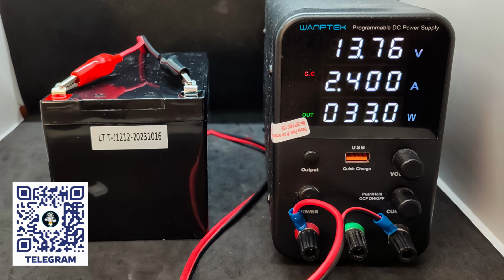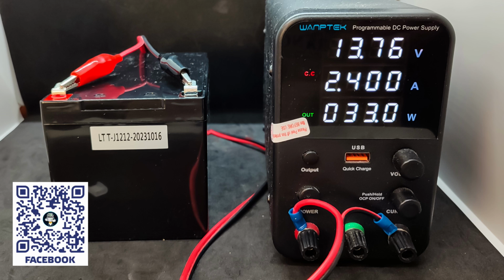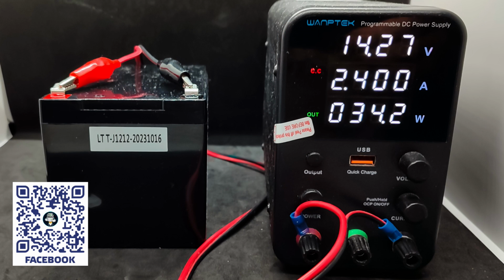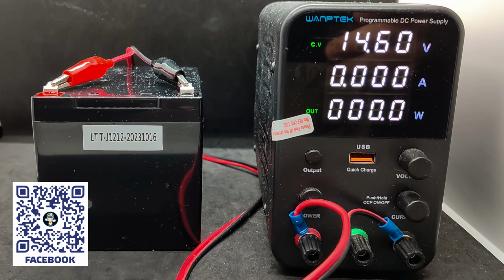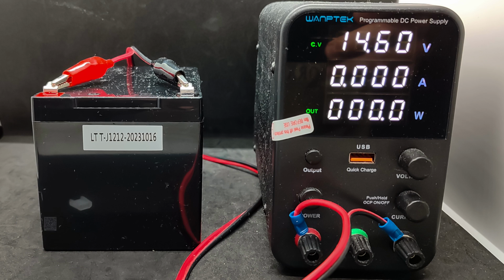I'm powering the battery now. The unit is currently operating in constant current mode. The voltage on the battery is 13.76 volts. That's the level it arrived at. As charging progresses, the voltage rises. I remind you that for full charge, you need to set 14.6 volts. However, in uninterruptible power supplies, batteries are not charged to 100%. A buffer mode is used there. After the voltage reached its maximum, the BMS disconnected the battery cells from charging. The current dropped to zero.